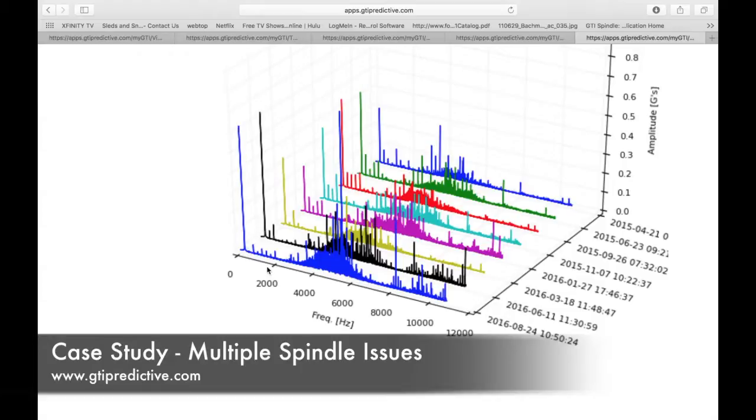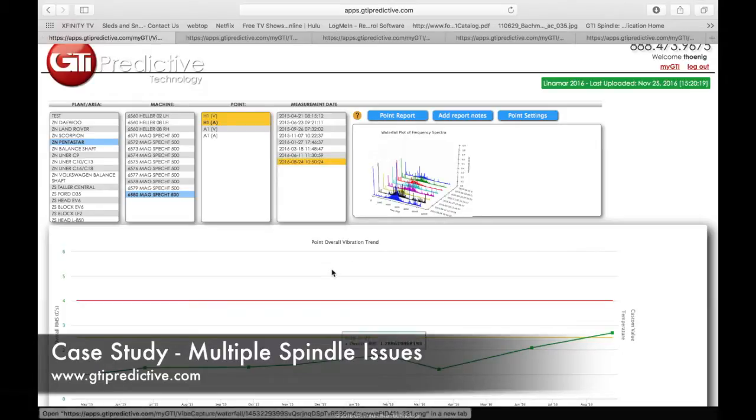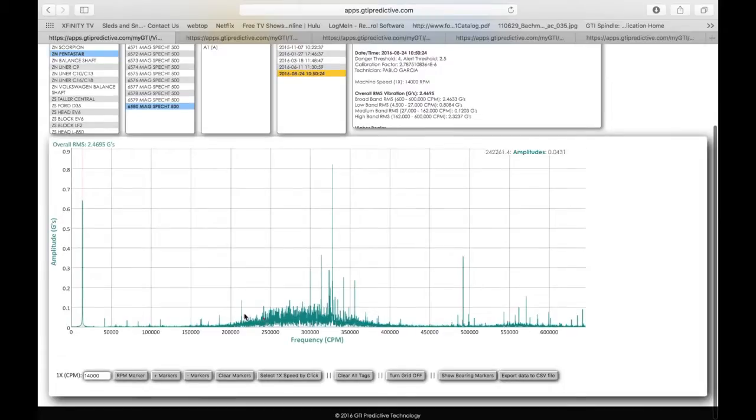Again, you can see the power of this tool, and we're just crossing the yellow threshold. So what we're seeing here as we drill into our last reading and spectrum, yes, we do have bearing defect frequencies.